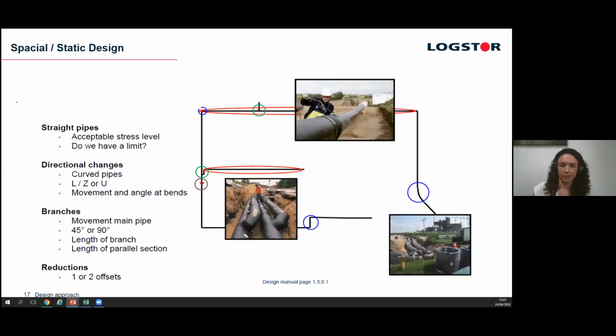So that will naturally introduce Z-bends or elbows where they need to go around corners, for example, or if you need to go around a manhole, as another example, that would naturally put in a U-loop. These can then be used to mitigate your expansion.